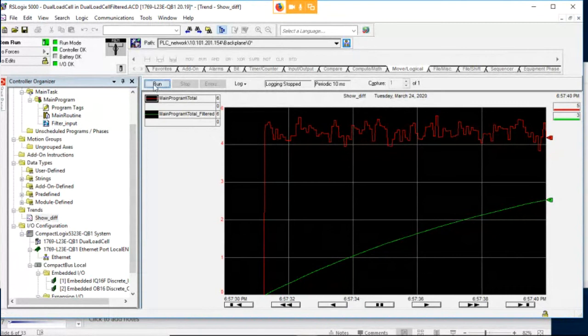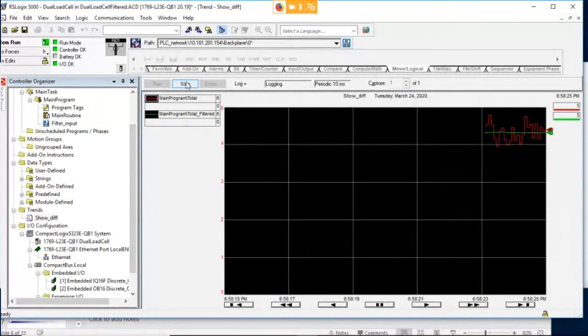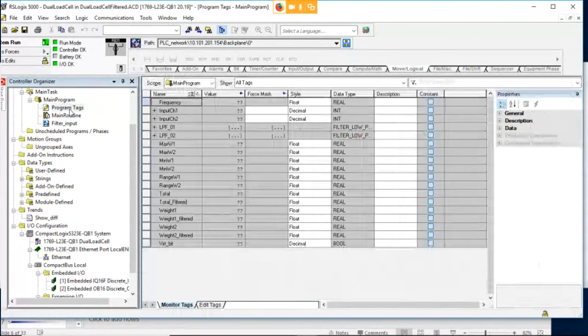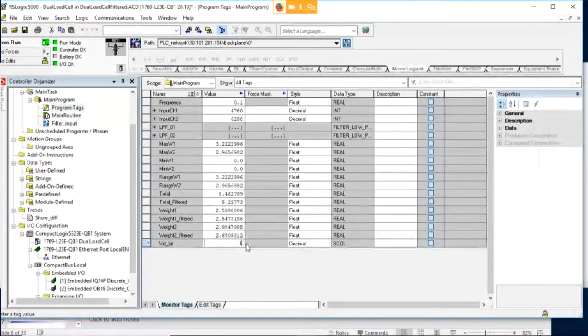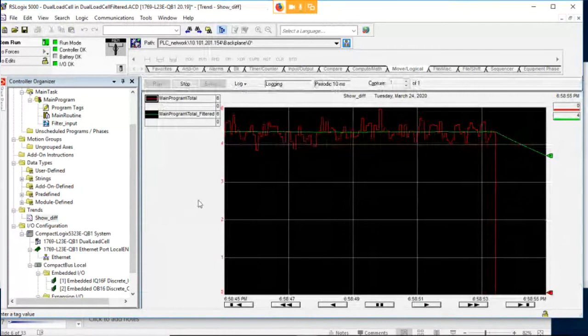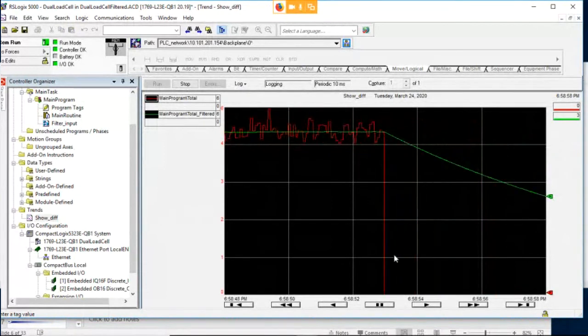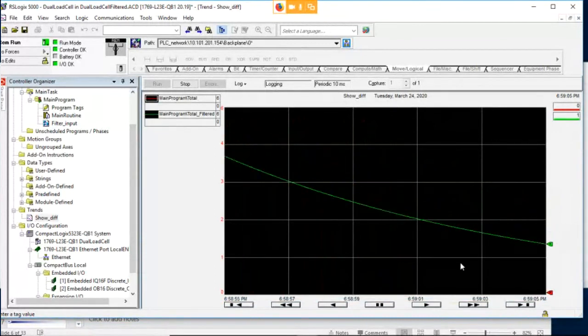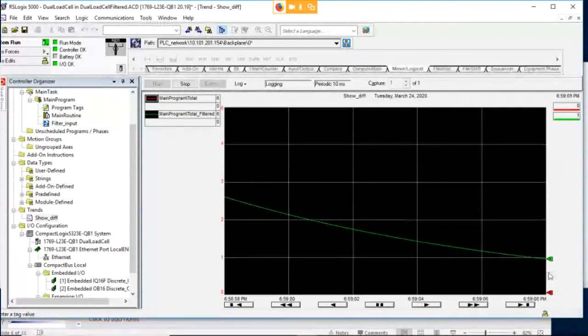Okay, so now remember, when I hit run, it jumped up because we were just looking at the graph, but the filter had already gotten up there. And so that's why once I hit run again, it jumped immediately, because the filtering had been done and it got up there. So again, if we come back here and I set this back to a 1, flip back to my trend, right? The red immediately jumps back down to 0, but the filter takes a while to get down there because it's kind of trying to forget everything now.